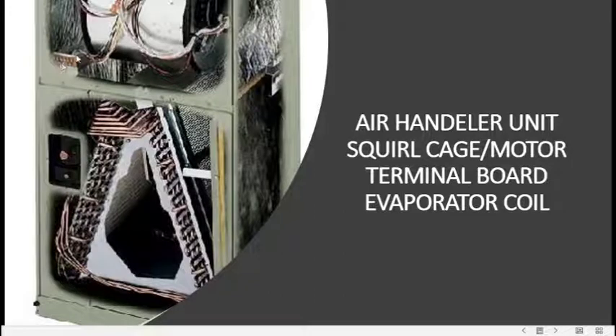When in cooling mode, this will energize your fan motor. Sometimes you have a delay, and it also energizes your outdoor unit, which this is your suction line, and this is your liquid line. The suction line goes back out to the unit. Your liquid line comes from the unit and gets distributed to a low pressure gas through your evaporator coil. Right here we've got a filter system. Here we show insulation throughout the unit.